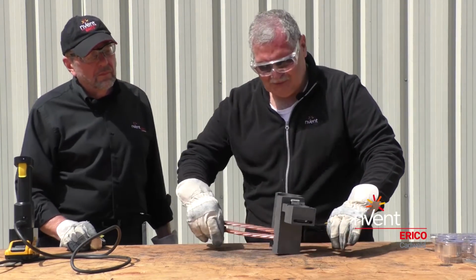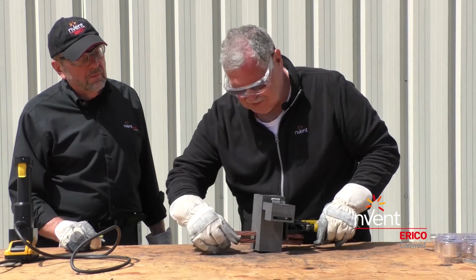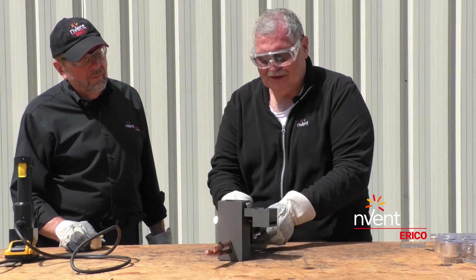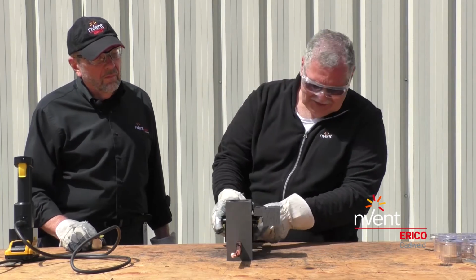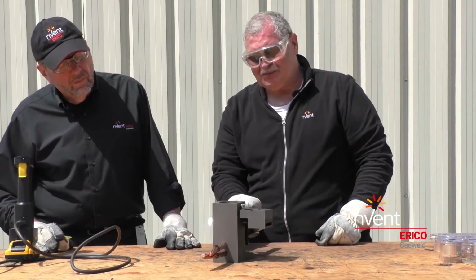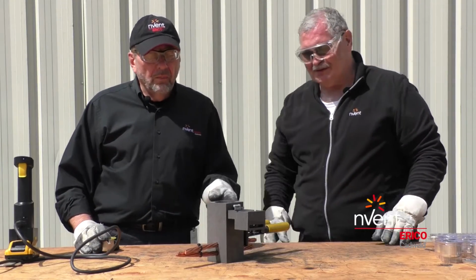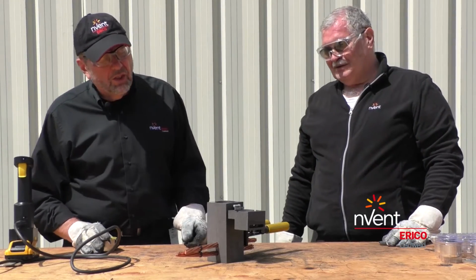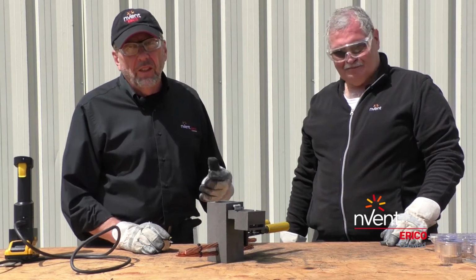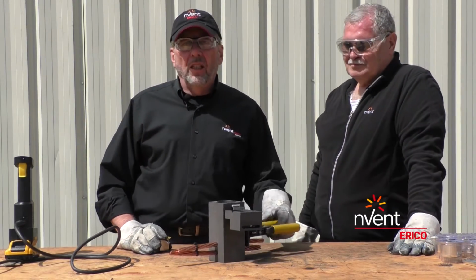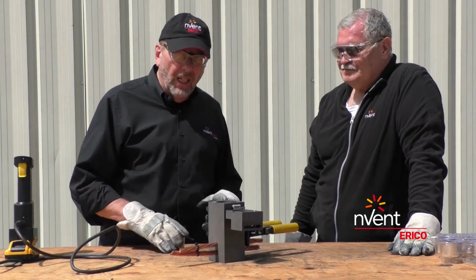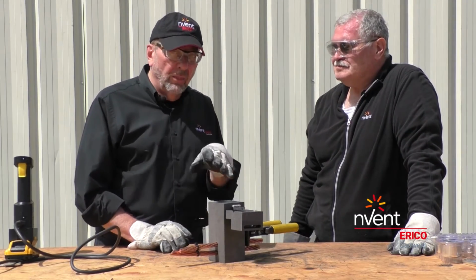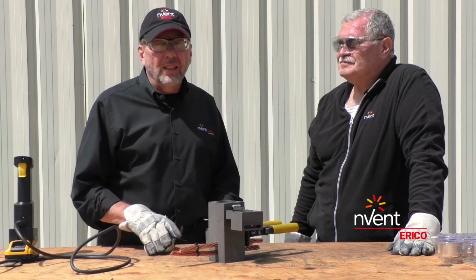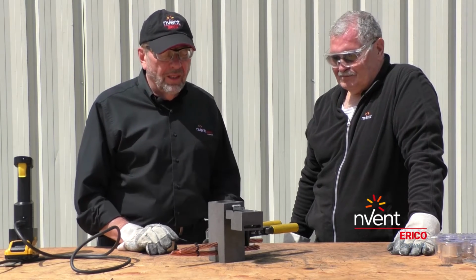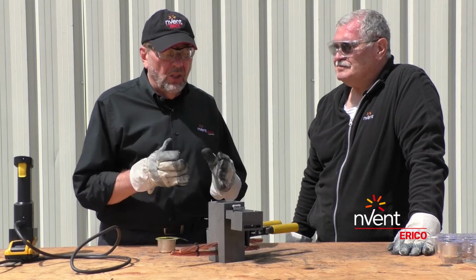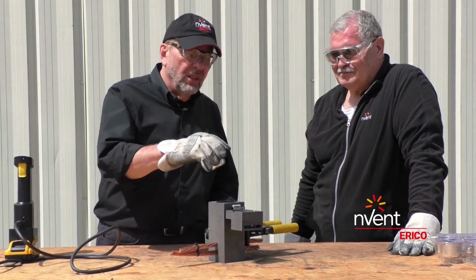Basically I'm going to take my cables, put them in the mold, lock the mold together, make sure my mold's sealed with no gaps in the split, and we should be ready to weld. We're making this connection with short sections of cable. In a real field training session, where the cables are very long, it takes a little more finesse to get them in the mold, but the glorious thing about this mold is once you get them aligned and close it, you're good to go. So we'll drop in our plus cup.